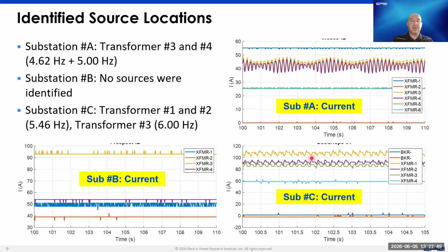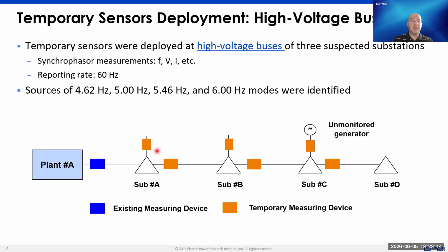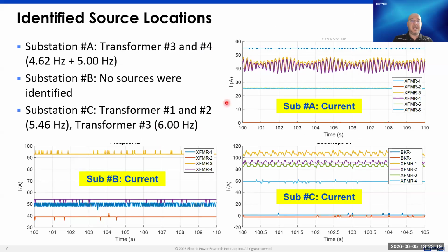And then substation C, from three transformers. Actually, for transformers 1 and 2, we could see oscillations at 5.46, and for transformer 3, we could see them at 6 hertz. So that was based on analysis of the data at those substations A, B and C, at the high voltage side. Then Entergy again talked to their customers, the industrial loads in these substations.